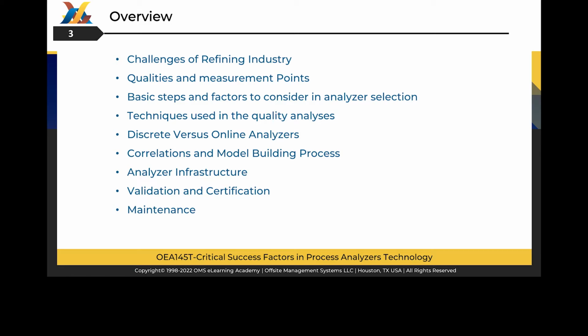A refinery uses multiplexed process online or discrete analyzers to measure incoming crude oil qualities and outgoing products. The measured qualities may be different crude oil and end-user products. Many analyzer technologies are available in the marketplace based on required quality analysis, sampling points and response time, etc. Hence, there are many critical factors to select, configure, and commission a turnkey analyzer system. It is necessary to validate, certify, and maintain the analysis models and infrastructure. This topic discusses all the above considerations in detail.